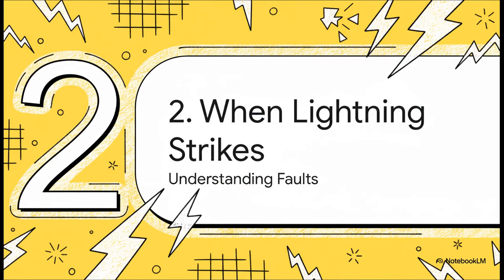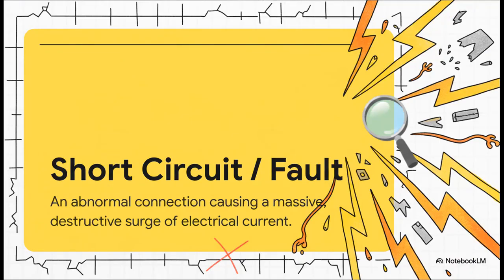So let's talk about the problem this whole system is built to solve. What actually happens when the grid is, for lack of a better word, under attack? A fault, or a short circuit, is basically an electrical wound. It's an accidental path for electricity to take, and that causes a colossal, unimaginable surge of current. This surge is so powerful, it's incredibly destructive. It can literally melt metal conductors, destroy millions of dollars of equipment, and just completely destabilize the grid.